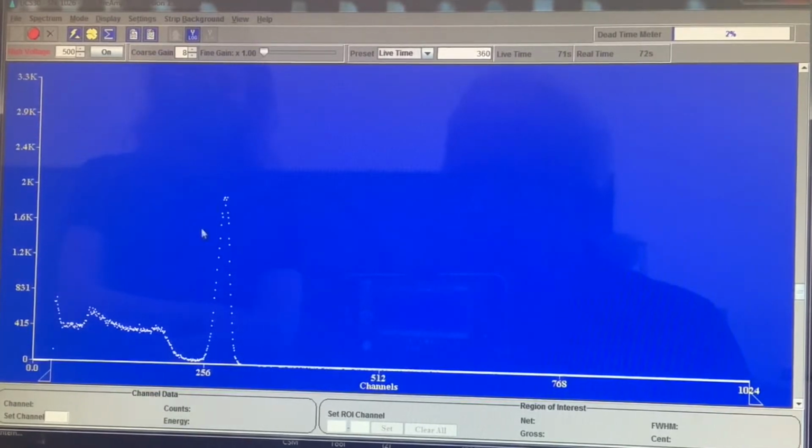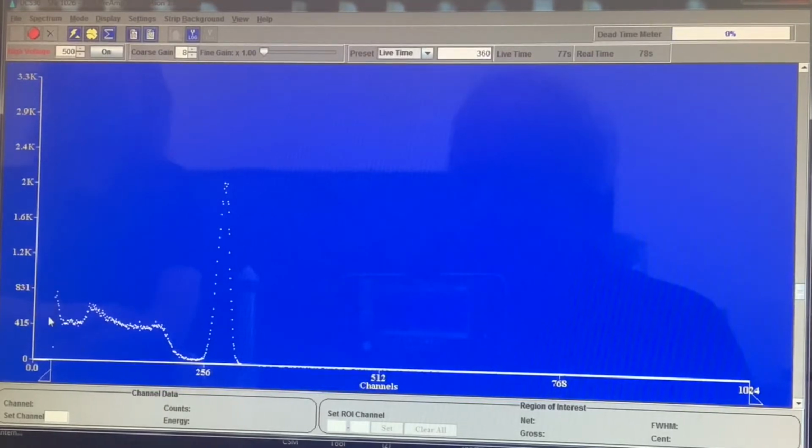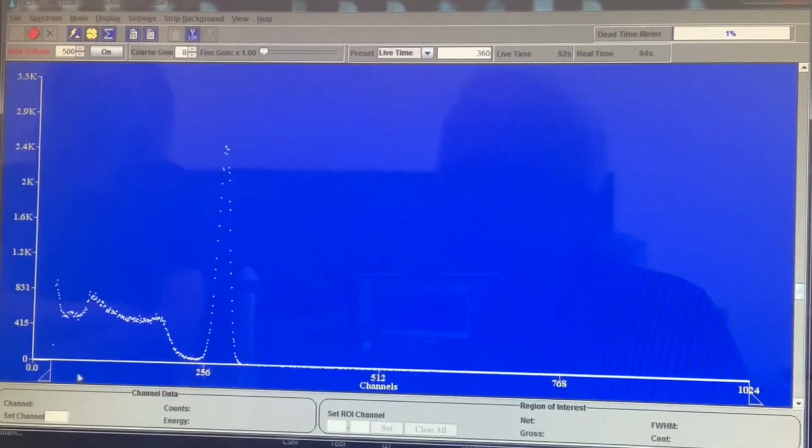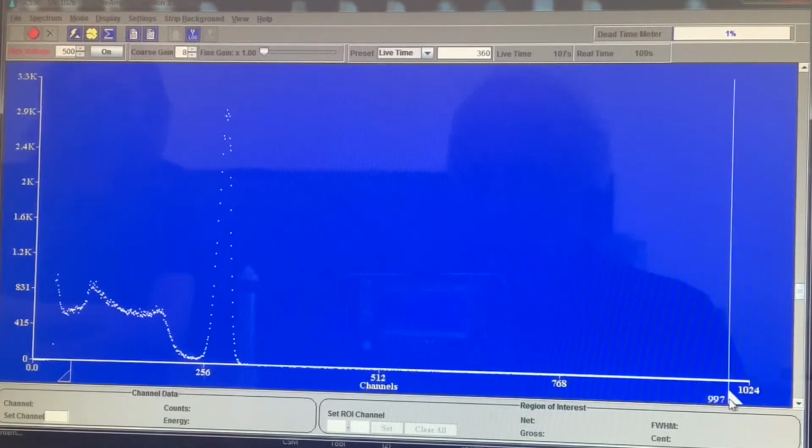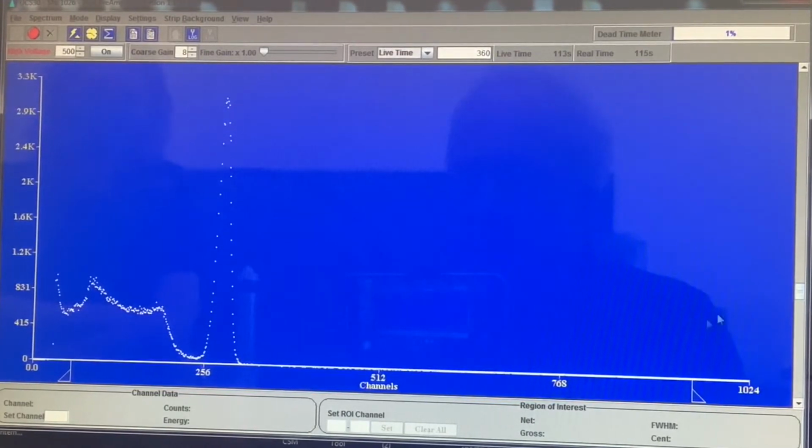So this is the main gamma ray coming out of our source, and this is a bunch of stuff that we will talk about in lab number 2. Since we're simply interested in the principal gamma at 662 keV, we're interested in this feature here. So I can take this slide here and move it out here, and then I will stop counting anything below that. That's my lower level discriminator, and I have an upper level discriminator over here, which would then eliminate any counts above that value. So I'm still collecting, and we can see that the gamma peak is growing in amplitude here.